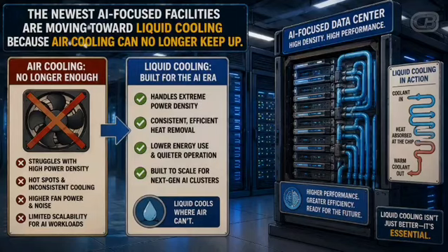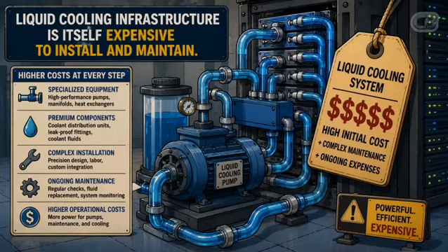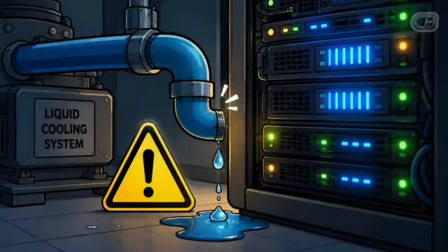The newest AI-focused facilities, with their much higher power density per server rack, are increasingly moving toward liquid cooling systems specifically because air cooling can no longer keep up. But liquid cooling infrastructure is itself expensive to install and maintain, and it introduces an entirely new category of mechanical failure risk directly adjacent to sensitive computing equipment.